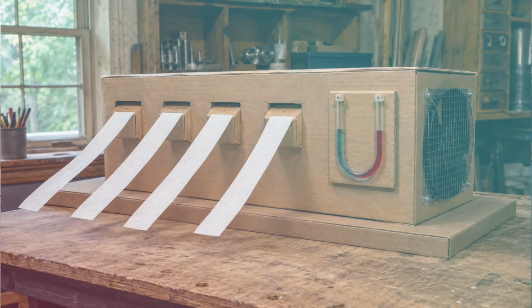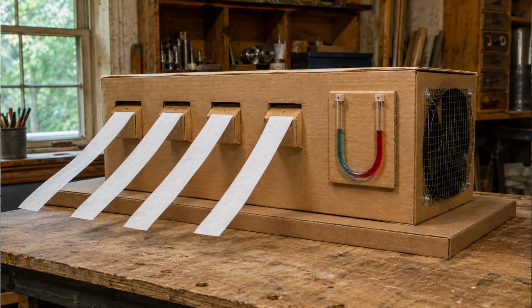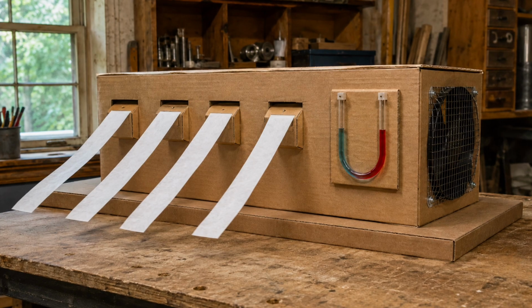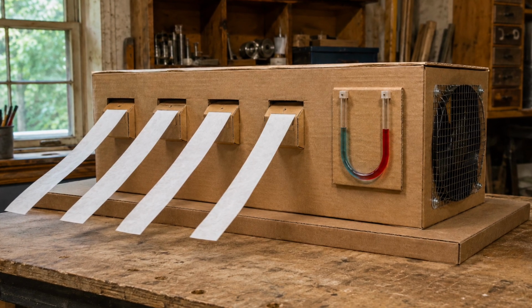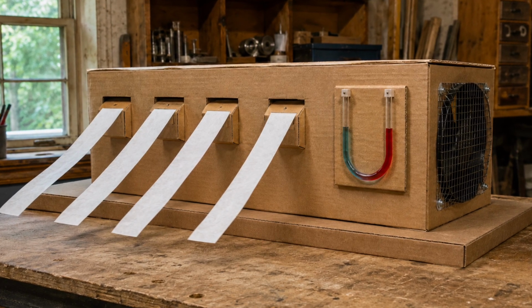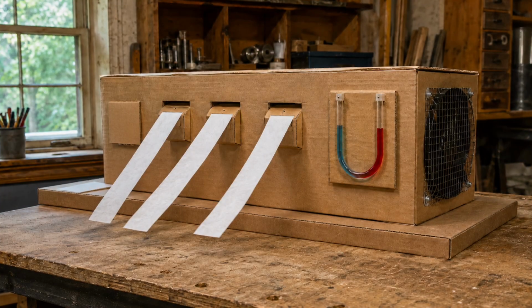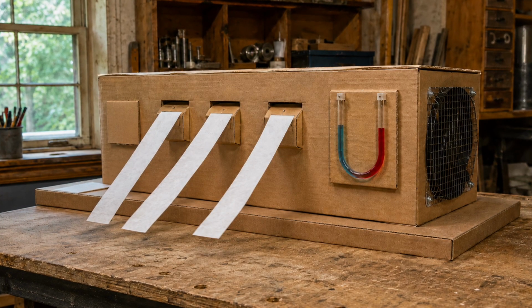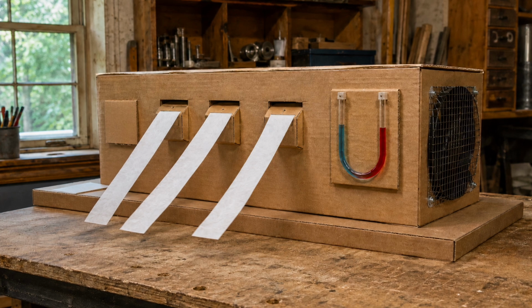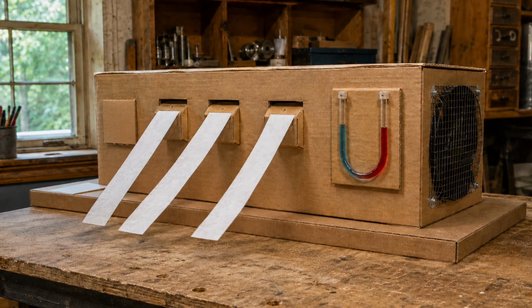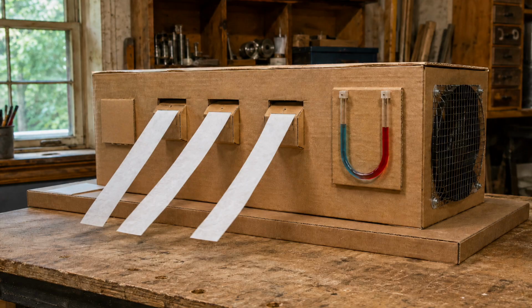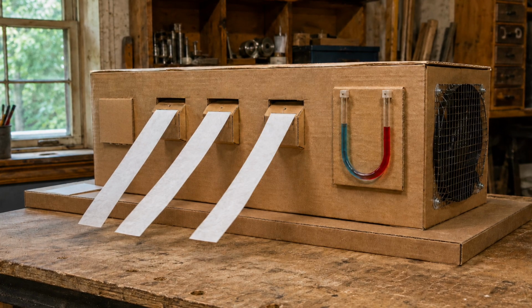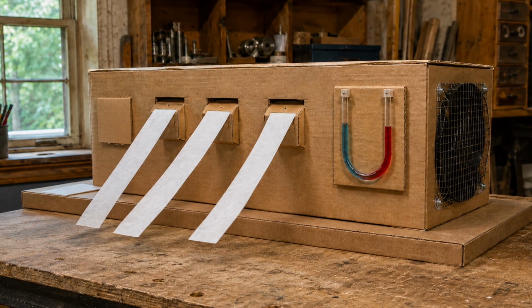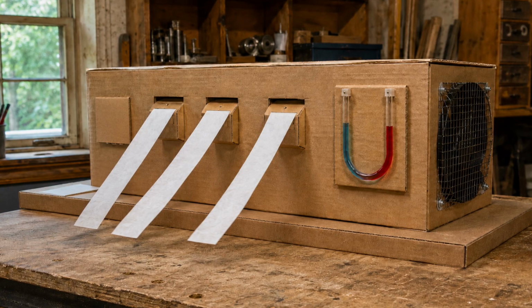Fan on. Look, 4 streamers, all lifting, all moving about the same. The air has 4 open paths out of the box. Look at the pressure gauge too, and remember where the colored water sits. Now I close one room. A flap of cardboard over the first hole, my empty guest room. Watch the other 3 streamers, but watch the gauge as well. Some air crowds toward the opening still available, and the pressure near the fan rises. The fan was not told to slow down. We simply removed one of its paths.